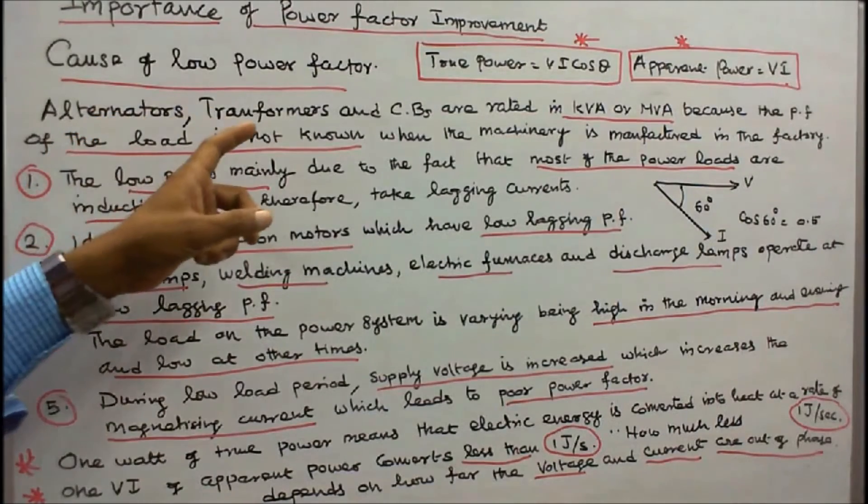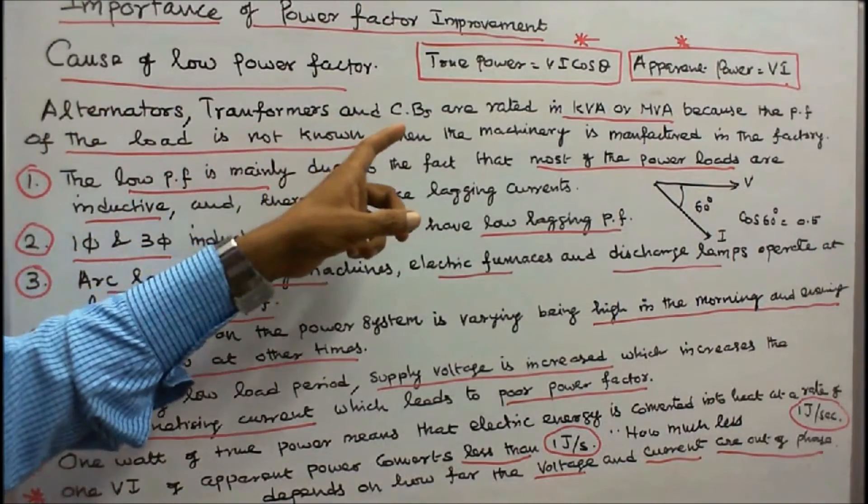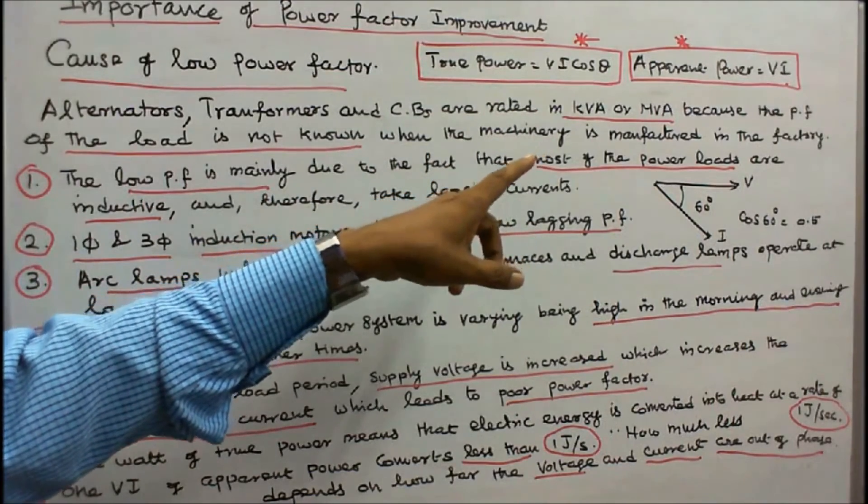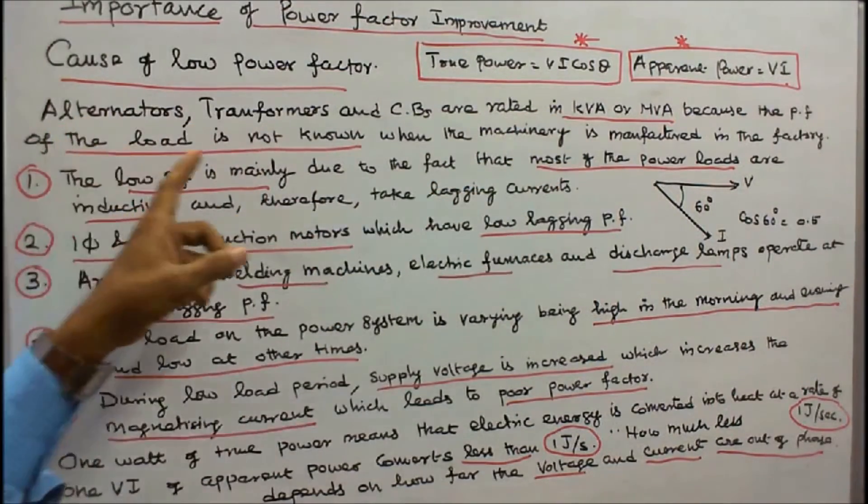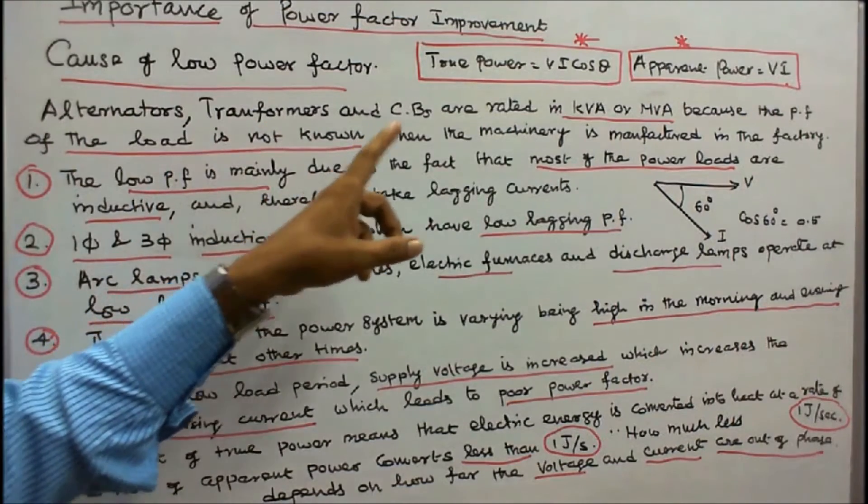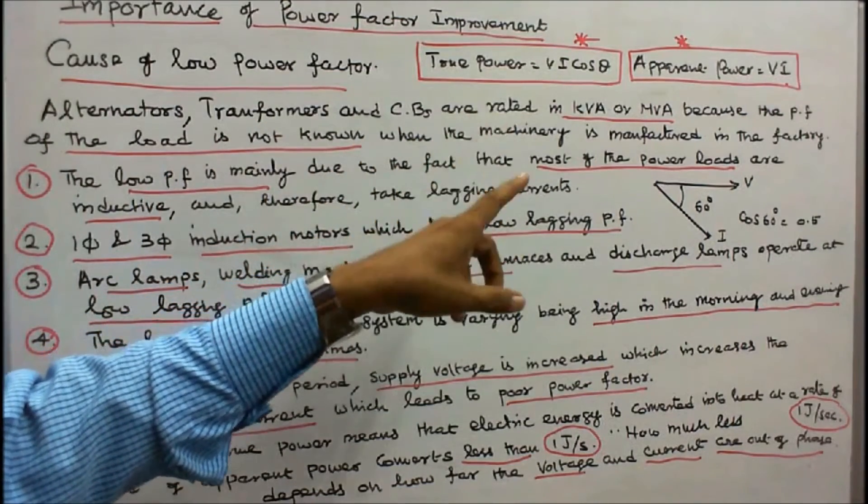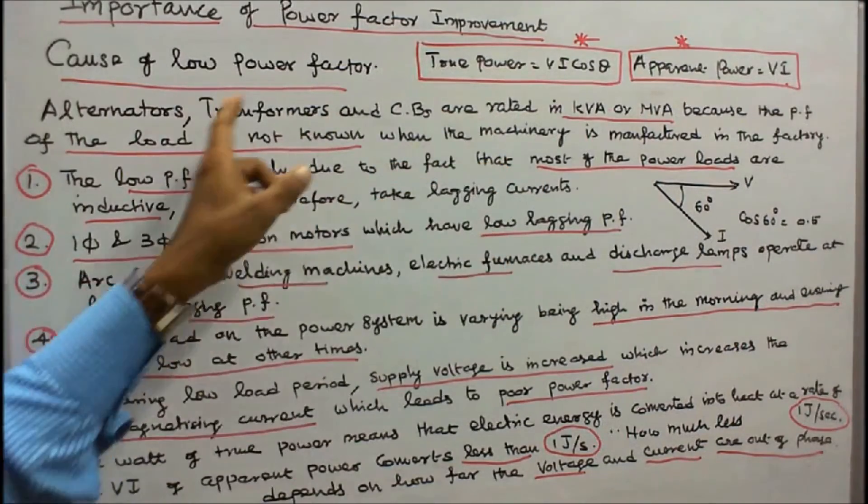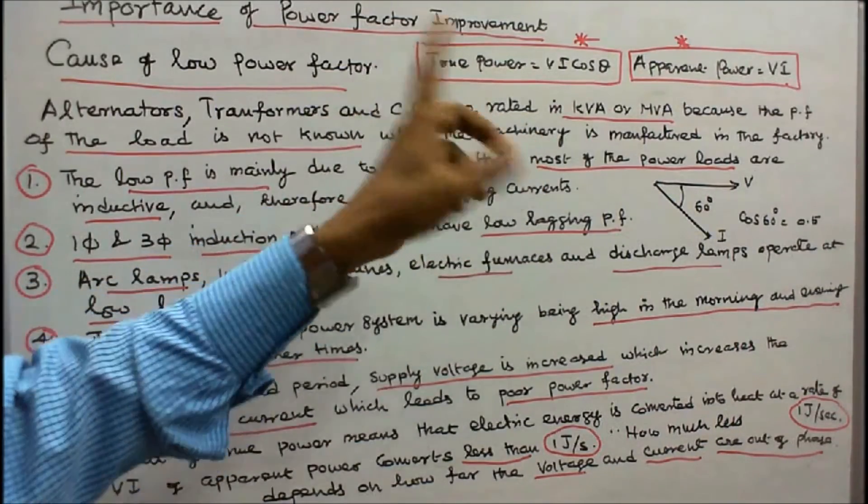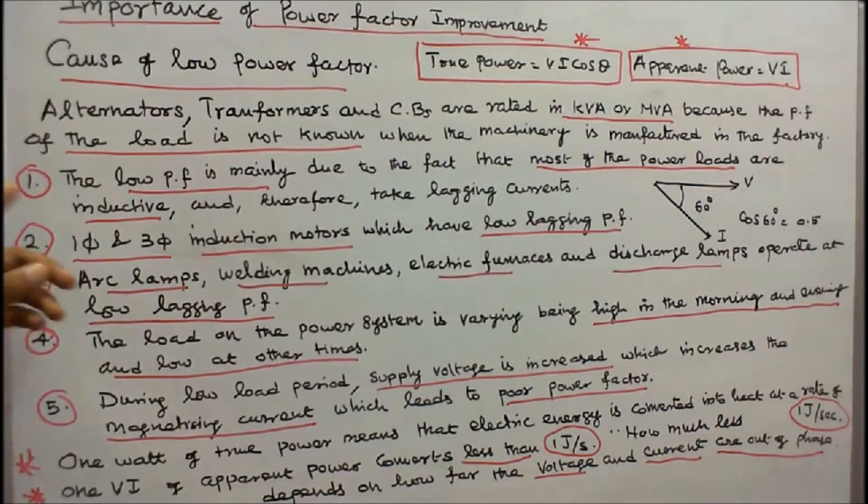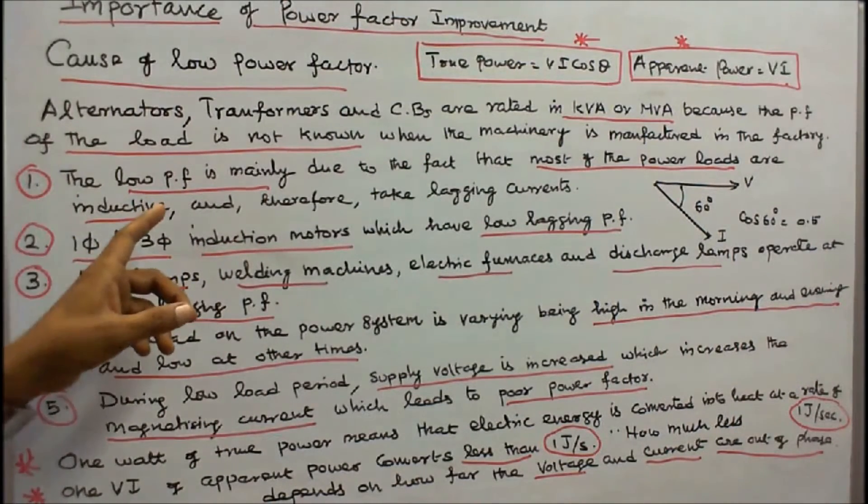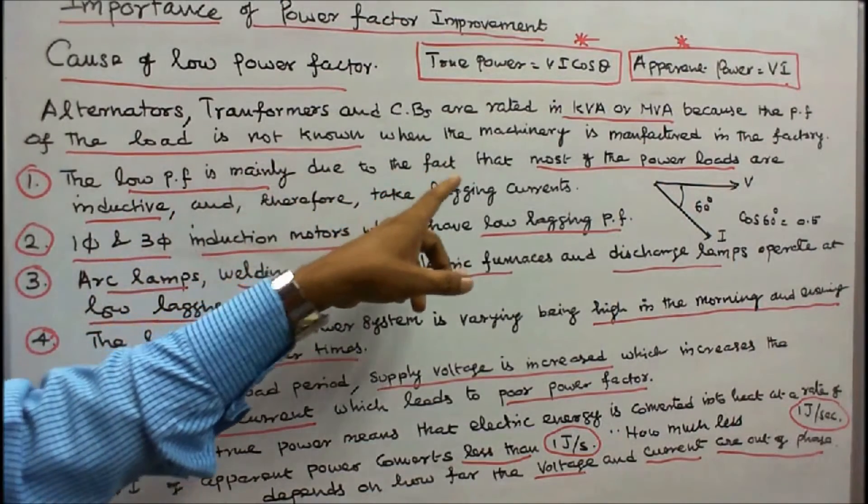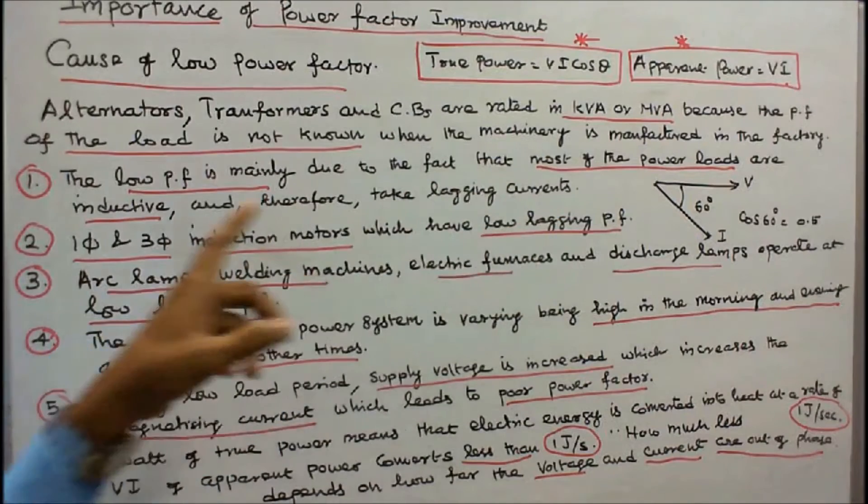Alternators, transformers, and circuit breakers are rated in kVA or MVA because the power factor of the load is not known when the machinery is manufactured in the factory. That is the reason they are rated in kVA or MVA.